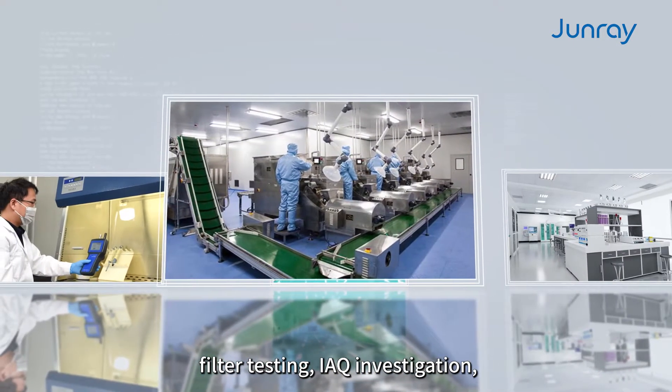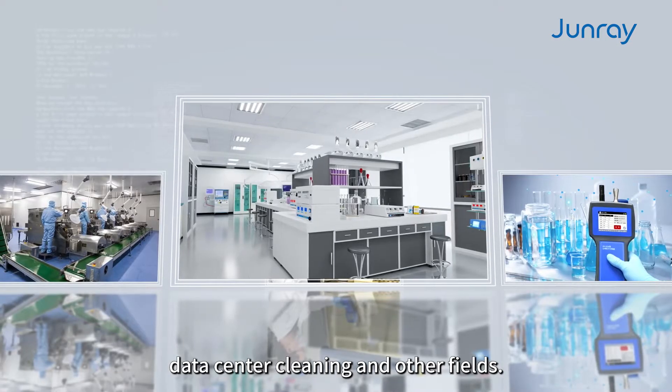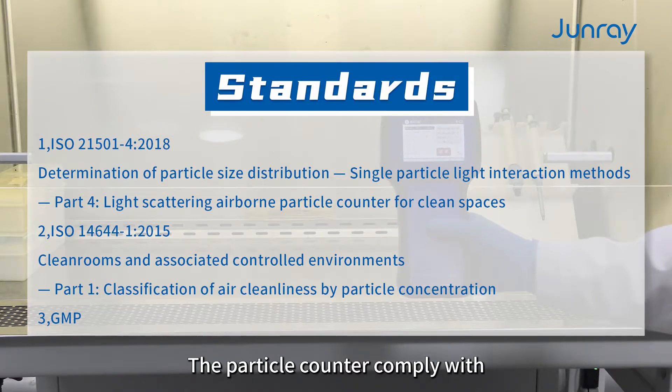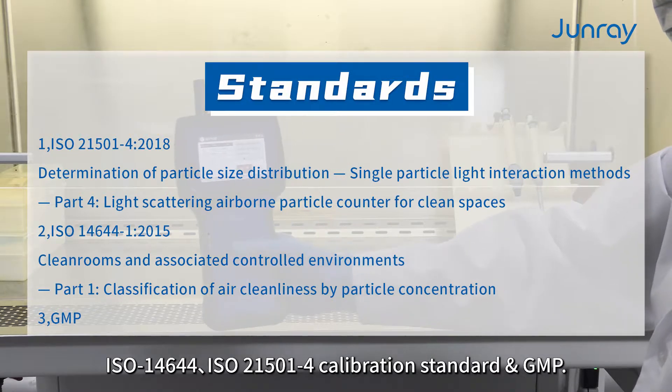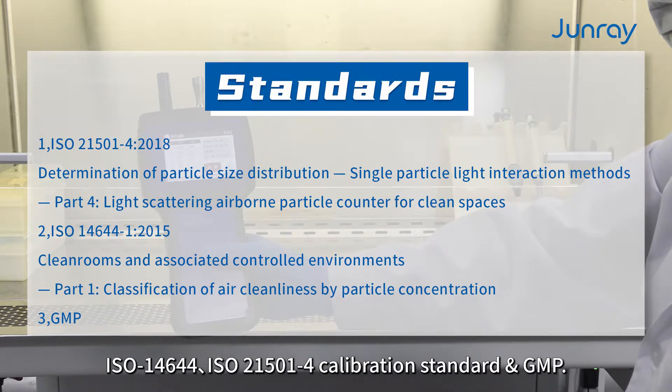It is mainly used in cleanroom operating room monitoring and verification, filter testing, IAQ investigation, data center cleaning, and other fields. The particle counter complies with ISO 14644, ISO 21501-4, and calibration standard GMP.